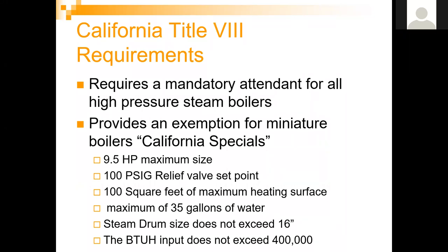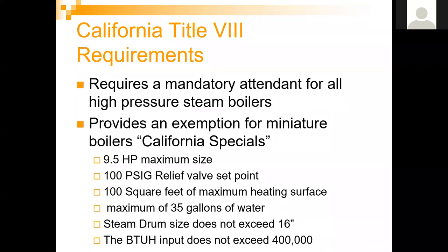California Title 8 is the fired pressure vessel code in the state of California. All fired pressure vessels, including boilers, must meet these requirements. For example, California Title 8 requires a high water alarm on all steam boilers — that is not a manufacturer standard and not required in most other states, but it is required in California. There are also requirements for redundant low water cutoffs on both high pressure and low pressure steam boilers, as well as requirements for hot water boilers and domestic water heaters.